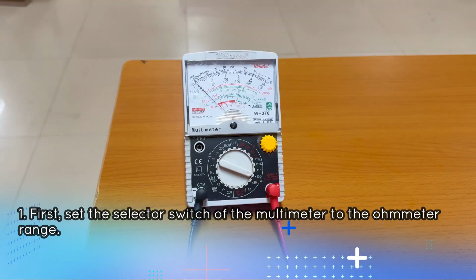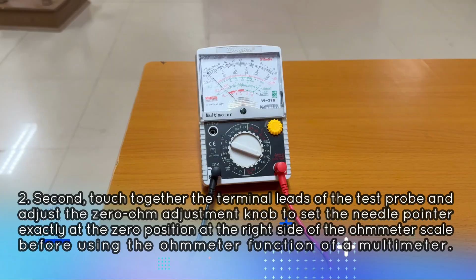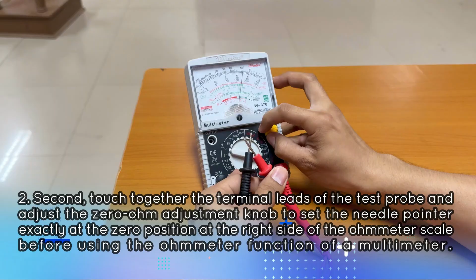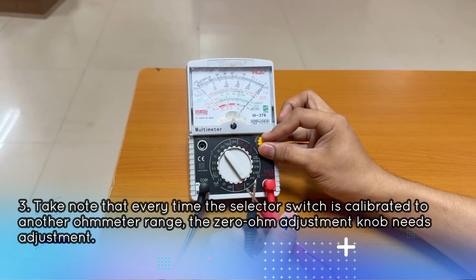If you are using an analog multimeter, first, set the selector switch of the multimeter to the ohmmeter range. Second, touch together the terminal leads of the test probe and adjust the 0 ohm adjustment knob to set the needle pointer exactly at the 0 position at the right side of the ohmmeter scale before using the ohmmeter function of a multimeter. This procedure must be performed to get the accurate result of checking the resistance. Take note that every time the selector switch is calibrated to another ohmmeter range, the 0 ohm adjustment knob needs adjustment.